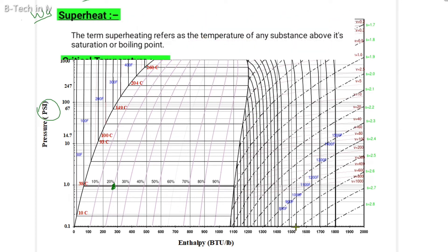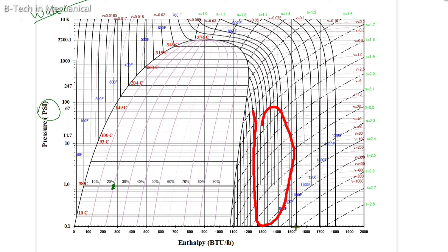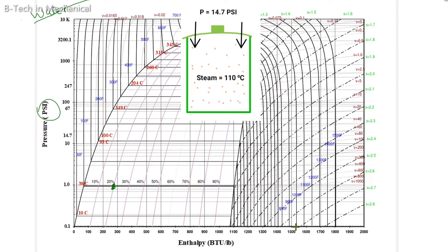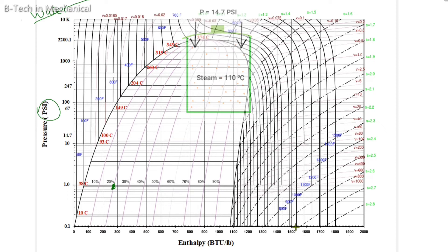Now, superheating. The term superheating refers to the temperature of any substance above its saturation or boiling point. A substance's superheating condition means its temperature goes above its saturation or boiling point, under any pressure — this is called the superheating condition, and on the PH chart it is shown to the right of the saturation vapor line. For example, if steam in a pot is under normal atmospheric pressure of 14.7 PSI and it is heated above 100°C — to 101, 102, or 110°C — that substance is in a superheated condition.